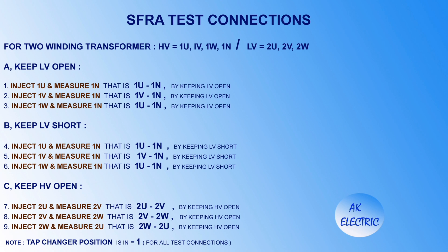For SFRA test connections on a two-winding transformer: with LV open, test 1U to 1N, 1V to 1N, and 1W to 1N. With LV shorted, test 1U to 1N, 1V to 1N, and 1W to 1N. Also with HV open, test 2U to 2V, 2V to 2W, and 2W to 2U. That gives a total of nine major connections. The tap changer position should be at one for all test connections.